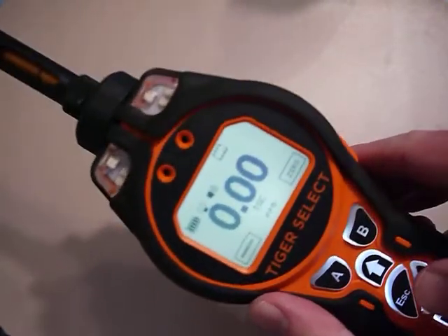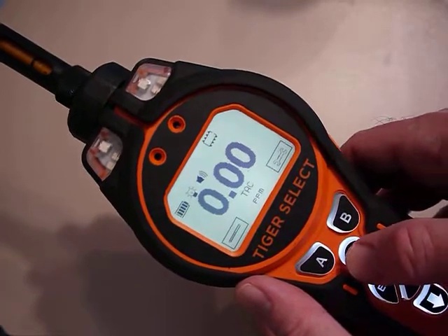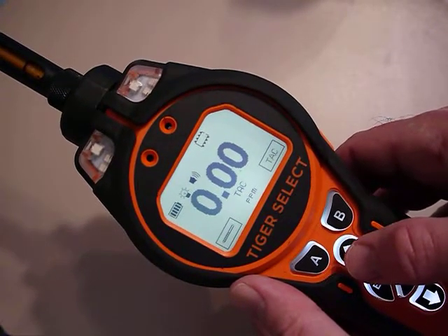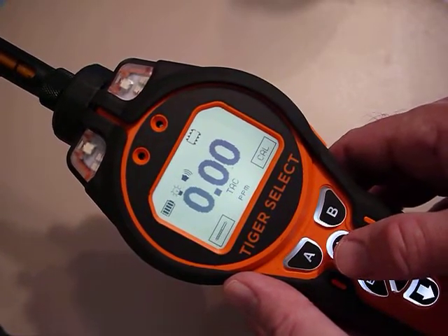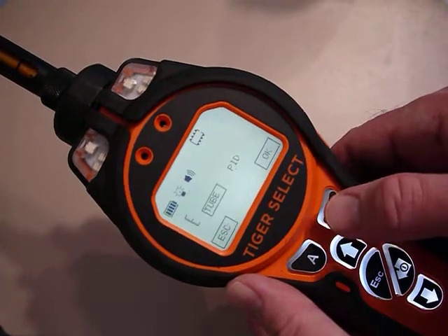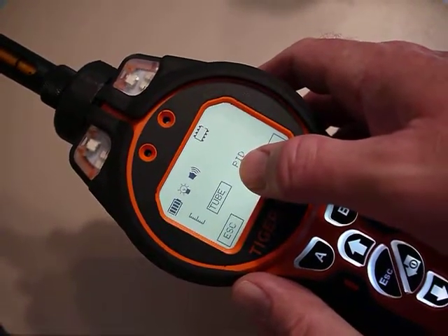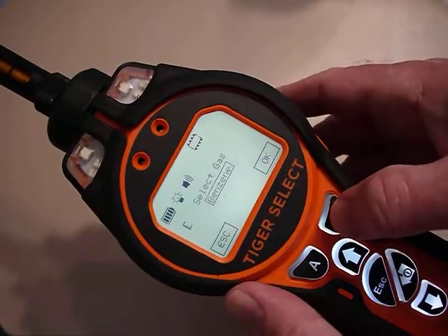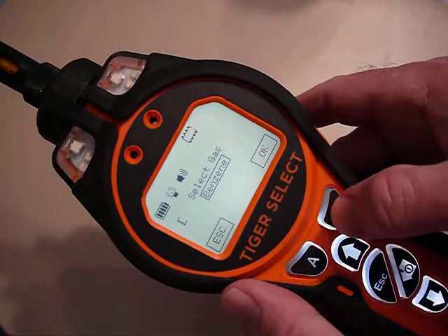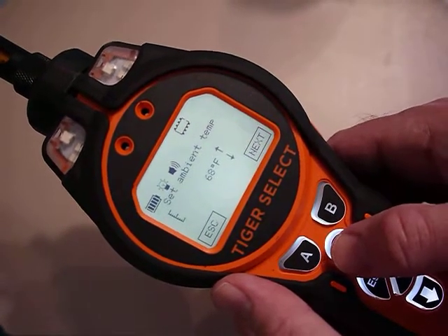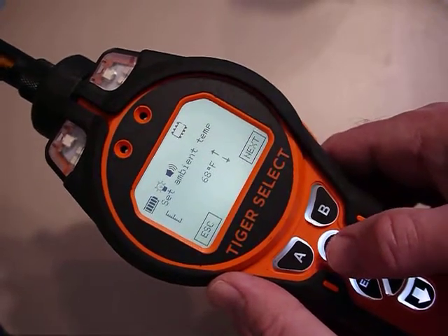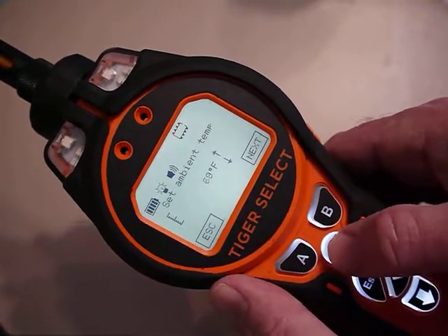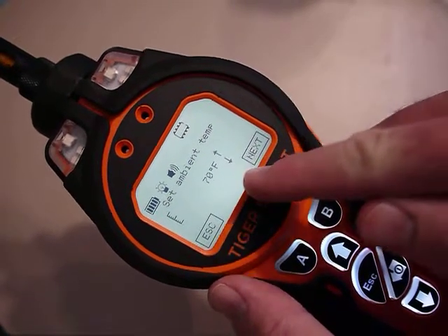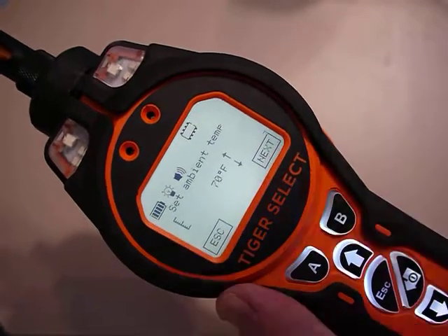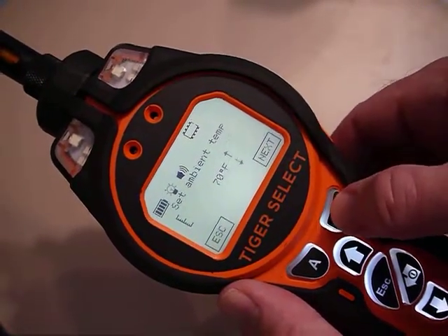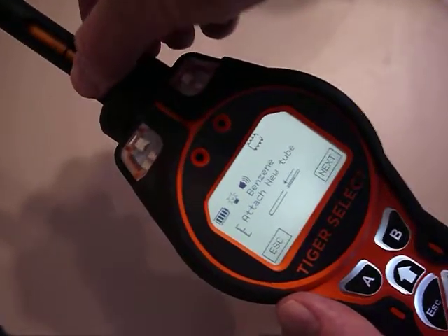So now I want to go back to calibration. Okay, so calibration, I select the B button where it says cal, and before I did the calibrate the PID, now I want to calibrate the tube, and it's highlighted, so I hit OK, and I want to calibrate for benzene, and it's asking me the temperature. I'm in Canada, I should set this to Celsius, but I know it's around 21 degrees Celsius, which is about 70 degrees Fahrenheit. So I've told it that, and next I'll hit next, and now it says put the tube in. So I've already got the new tube in place.